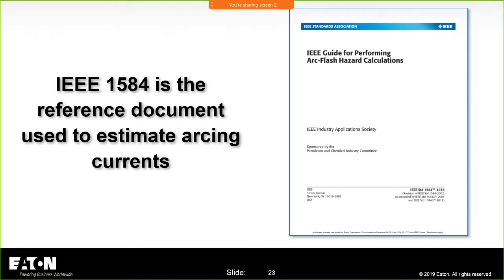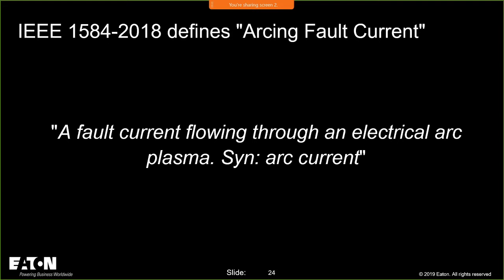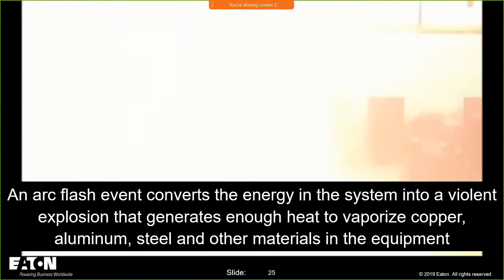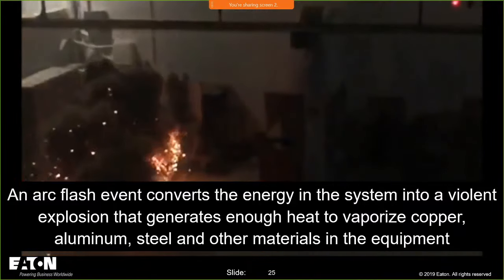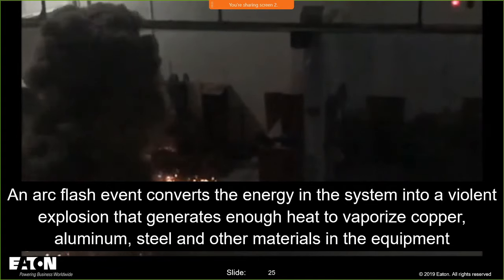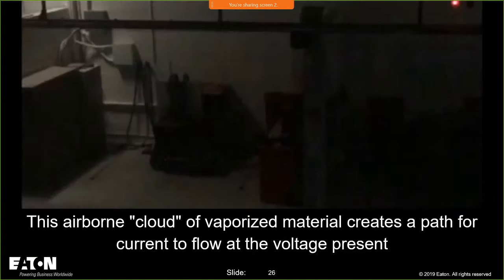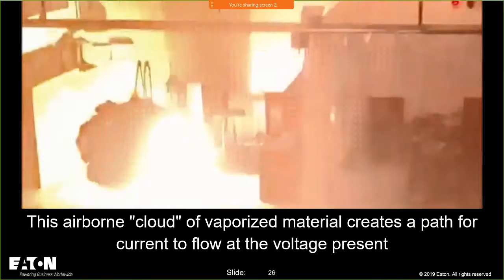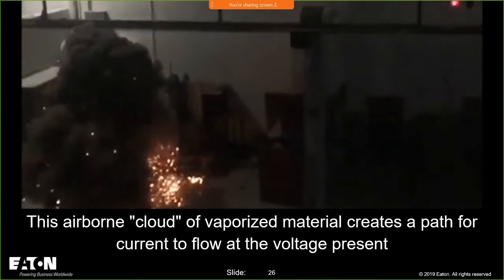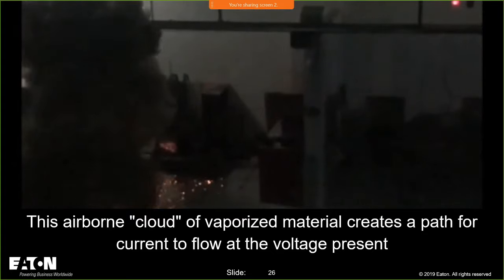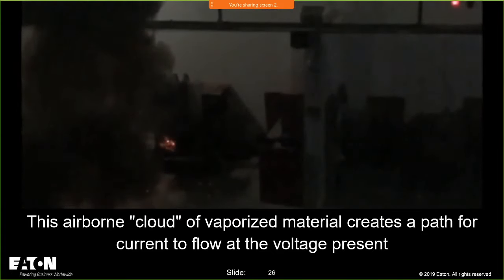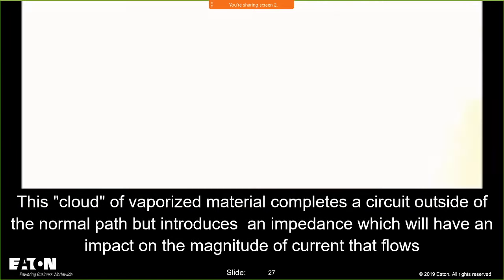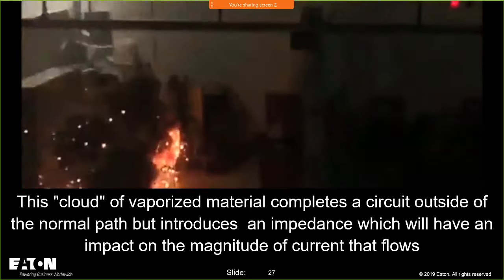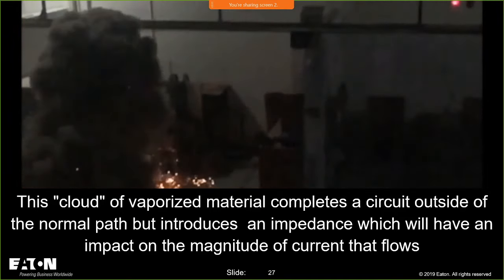There's all ink on slides. And they define an arcing current as a fault current flowing through an electrical arc plasma. Now, what is an arc plasma? An arc flash event is going to take the components that are inside of that piece of equipment and vaporize them. You're going to create a cloud of vaporized material that the current is going to flow through. So when current flows through this cloud of vaporized copper and steel and plastics and all of the different things that you're going to see inside of that cloud, I call it a plume, and I get made fun of, but I call it the plasma plume, and don't laugh, but that's what I call it.